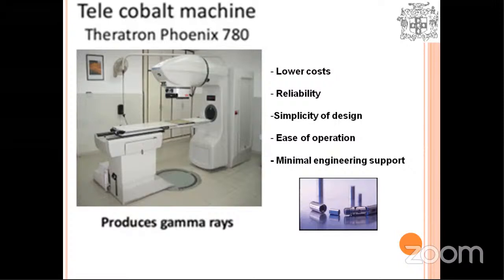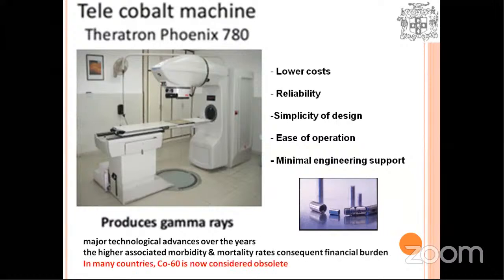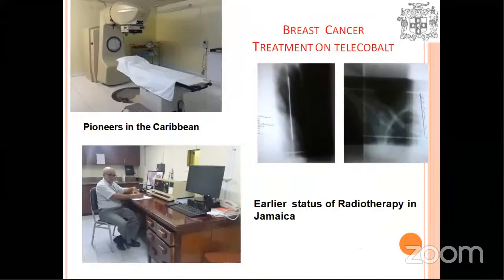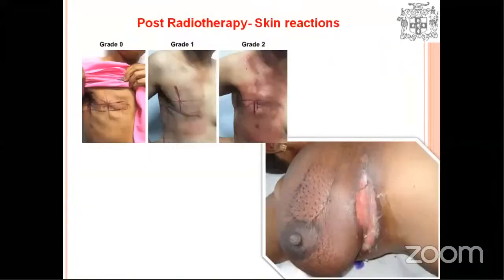Unfortunately, because of the simple nature of the machine, nothing much can be done about modulating the radiation beam coming out of the head of the machine, or shaping the beam. So a wide area of the patient is actually affected, and as a result, there is mortality and morbidity associated with these old cobalt machines.